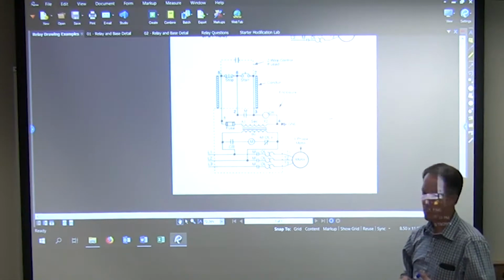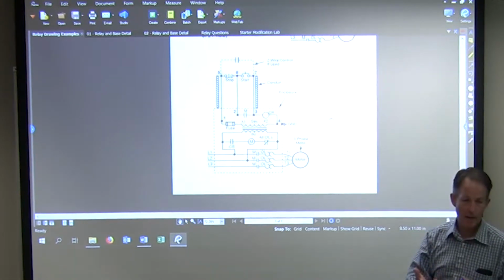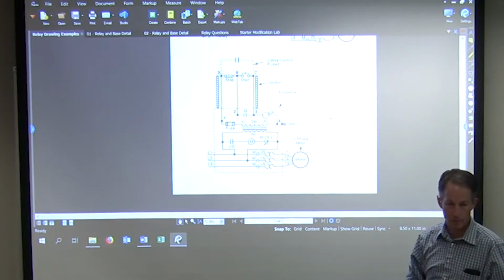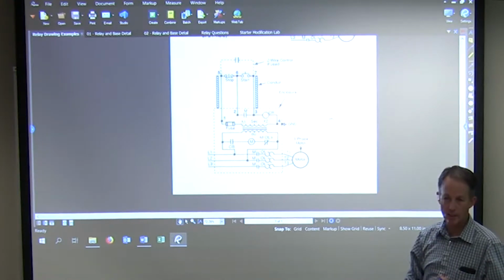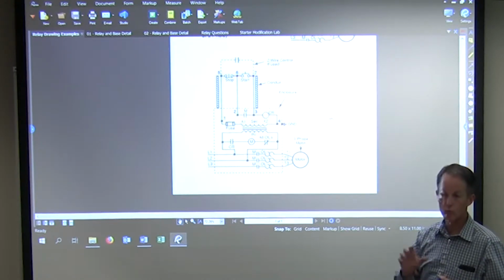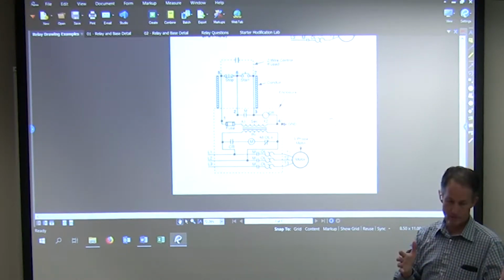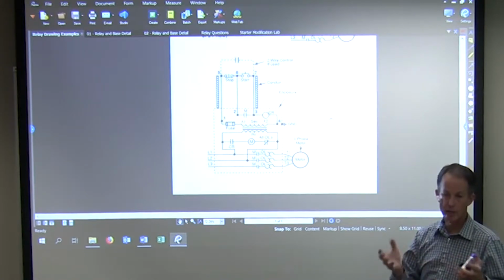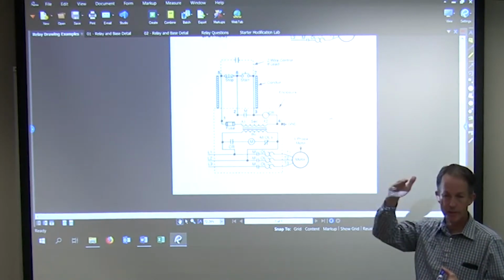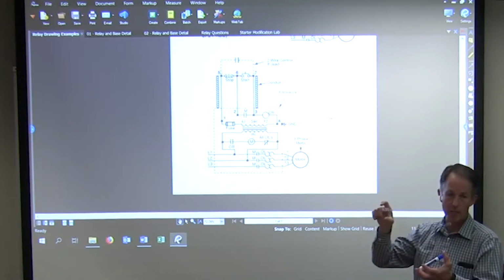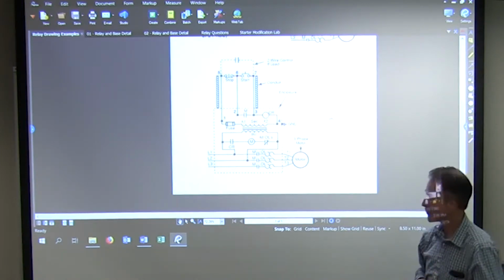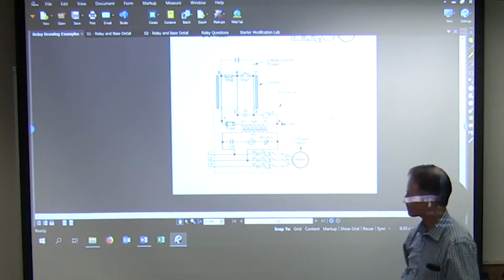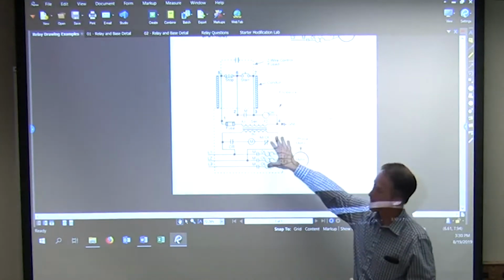So if I'm at 120 volts and I have a 240 VA transformer, what size fuse do I need? 240 VA at 120 volts, so I need a 2 amp, right? So I take your VA divided by the volts, that tells you the amp rating. Okay, so, yeah. All right, so what's happening in this circuit?